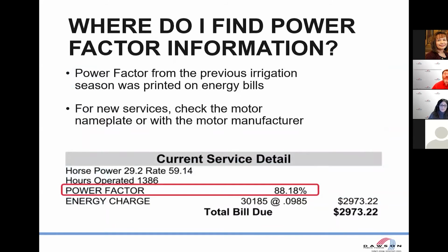All right, so here's where you can find your power factor information, right? If you've got a previous season's bill, particularly this fall's bill, look under the current service detail section there, and you'll see second from the bottom line there is power factor, right? This particular system has a power factor of 88.18%. They're awful close to 90. So that's going to be a real tough decision for them as to whether they need to improve or not. They may be okay with just paying the additional charge. It might be cheaper than having someone come put a capacitor on.